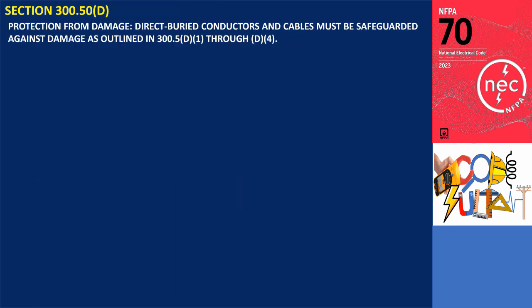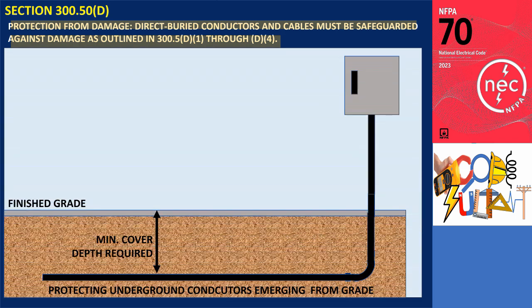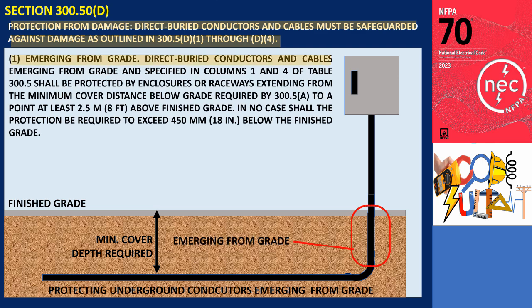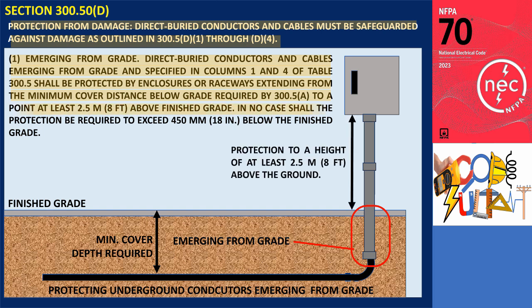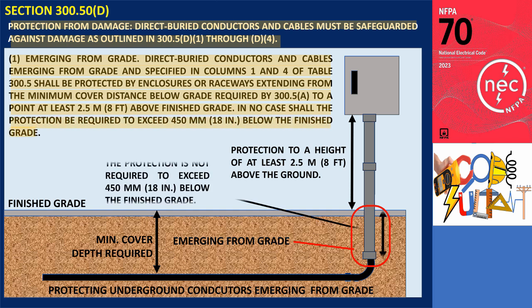Section 300.5(D), Protection from Damage. Direct buried conductors and cables shall be protected from damage in accordance with 300.5(D.1) through D.4. Section 300.5(D.1), Emerging from Grade: direct buried conductors and cables emerging from grade, as specified in Columns 1 and 4 of Table 300.5, shall be protected by enclosures or raceways extending from the minimum cover distance below grade required by 300.5(A) to a point at least 2.5 meters (8 feet) above finished grade. In no case shall the protection be required to exceed 450 millimeters (18 inches) below the finished grade.